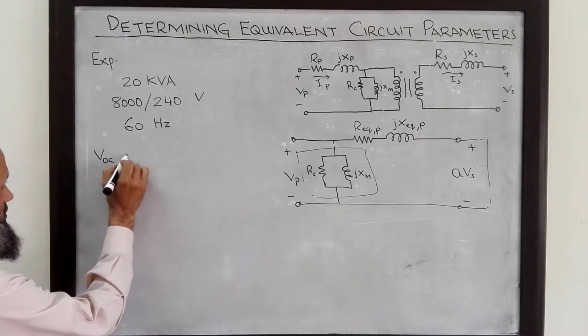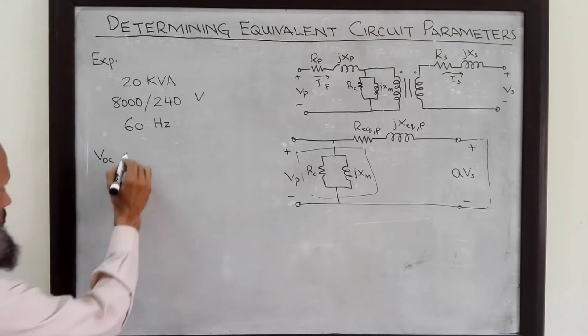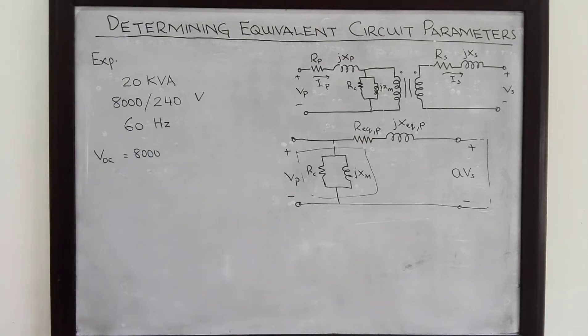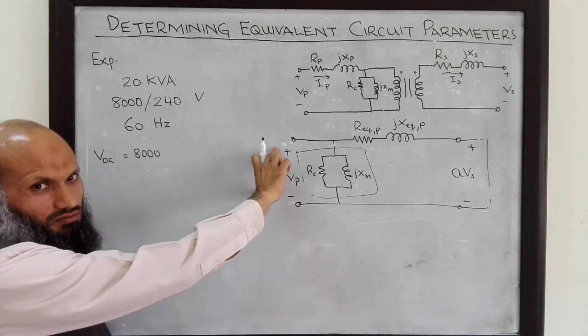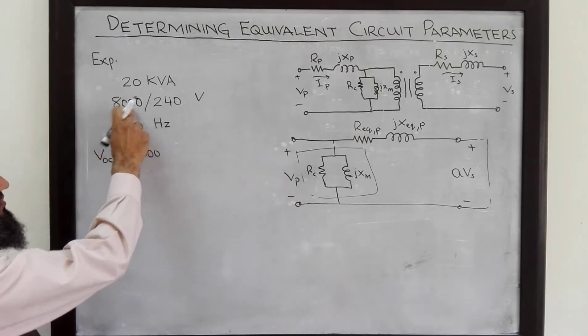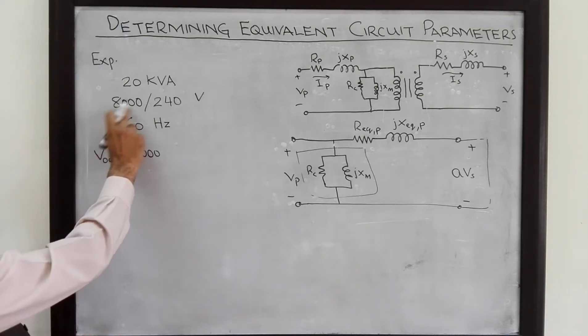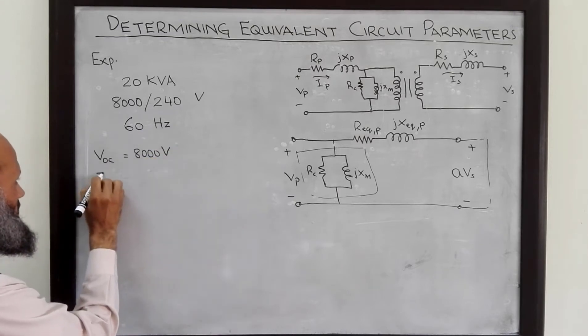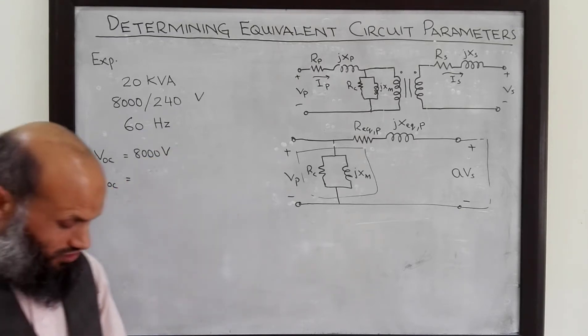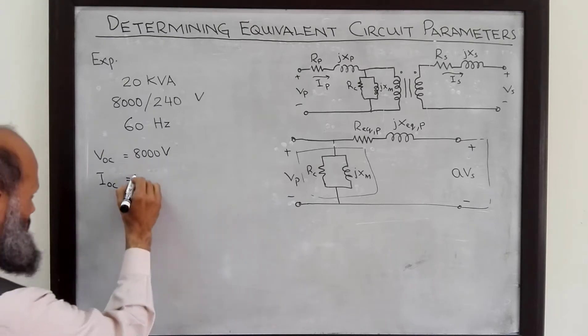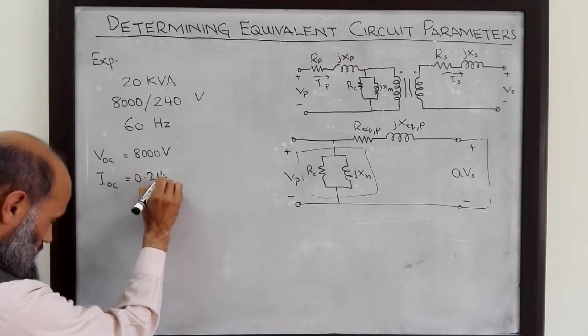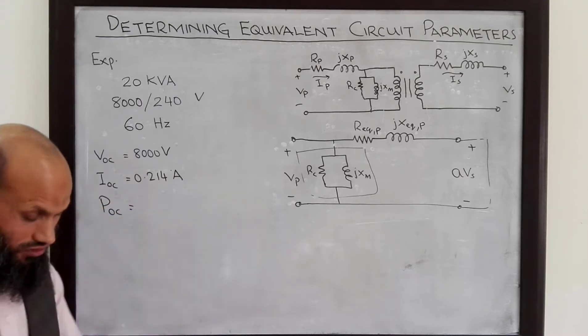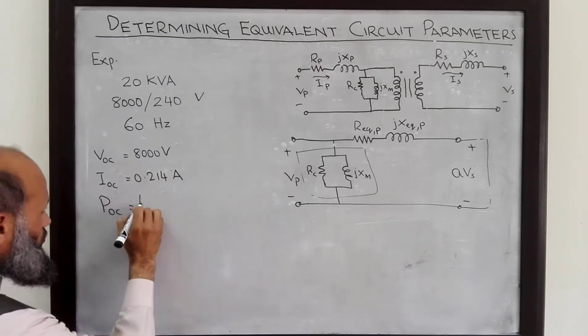The open circuit voltage that comes out to be equal to, we apply, remember when we perform open circuit test, we apply the rated voltage on the primary side. So, this transformer was rated for 8000 volts. So, we have applied this voltage and we measure the open circuit current. This is 0.214 amperes. We also measure the power open circuit. That is 400 watts.